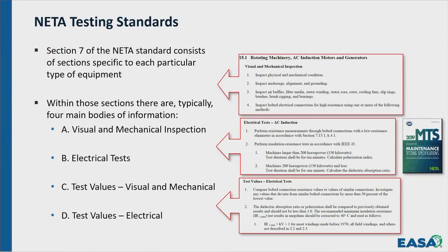Section 7 of the standard covers particular types of equipment, about 25 categories. One of them is rotating machinery, and it gives you visual and mechanical inspections—what to do—and electrical tests, along with test values. Some of those visual and mechanical tests have an expected result, some don't; the ones that do list the expected result. For electrical tests, there's always an expected result—you wouldn't be doing a test if you didn't get one.